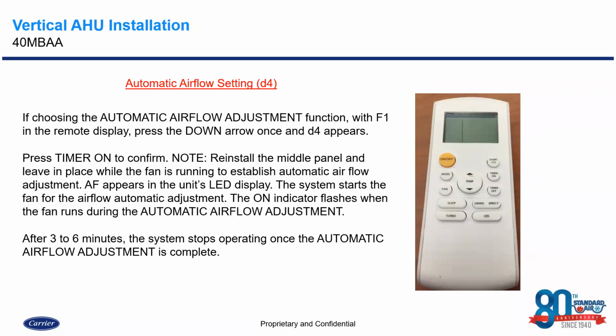Now when you get into the F1 setting, you'd want to hit the down temperature arrow until you see this lowercase d 4 on here. This is the automatic airflow adjustment. When you're getting ready to set this up, you want to go ahead and point the wireless controller at the infrared receiver, that little white box we talked about earlier.